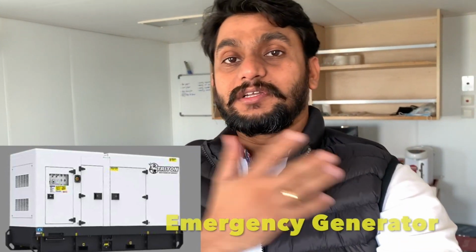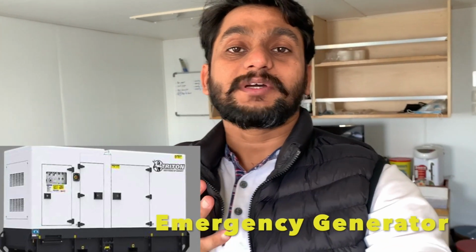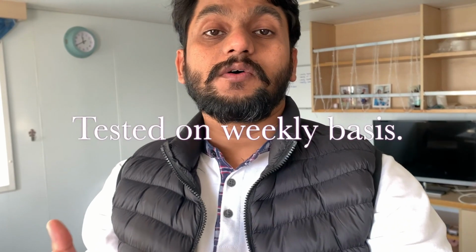So guys, you have seen in this video that if there is no power supply on board the ship, we can still survive on board with the help of the emergency generator, whose starting procedure I have already shown you. Normally the third engineer and chief engineer test this emergency generator weekly. They just test it on a weekly basis, so we make sure that the generator runs when there is no power supply.